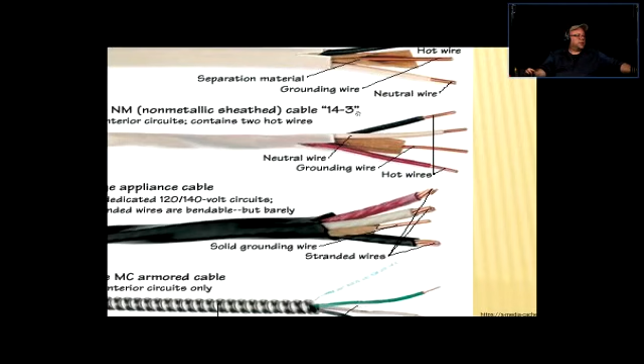Type non-metallic sheathed 14-3. An example, right? 14-3. 1, 2, 3, 4 cables or conductors. One of them is bare copper, which is the grounding or bonding, and the grounding or bonding wire should be either bare copper or green. Okay. So all the other ones are going to be hot, except for the white, which is the neutral wire. And the neutral and the bonding wire should be at the same potential. Even if they are not electrically connected, they still should be at the same potential, which would be the ground potential. So then we have the grounding wire or bonding wire, neutral, and then all the rest is hot, black and red.